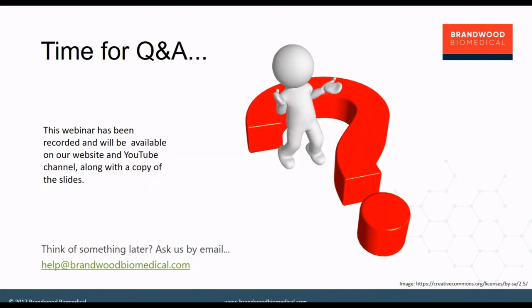Right. So, a question from Catherine. How do you build a technical file for several markets, and what kind of markets can typically be covered by the same technical file? Most of the markets that use the GHTF or IMDRF model can easily be supported by the technical file. But as we saw before, some of the artifacts that are put together as part of that technical file can also support some other applications, such as the 510(k) process in the US.